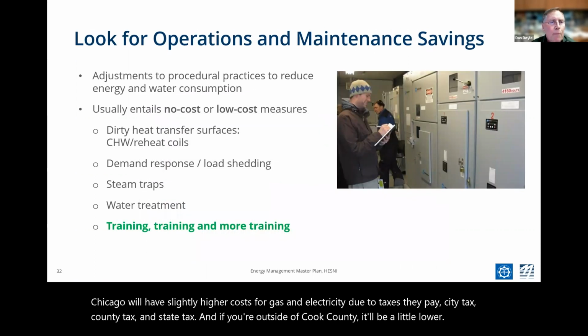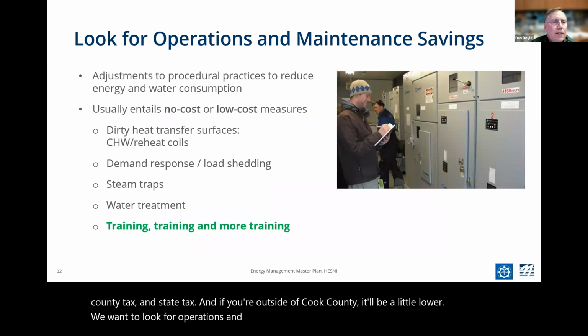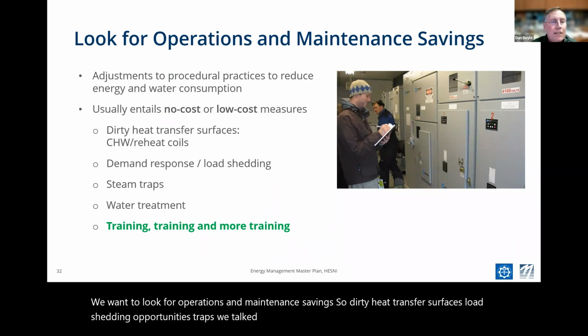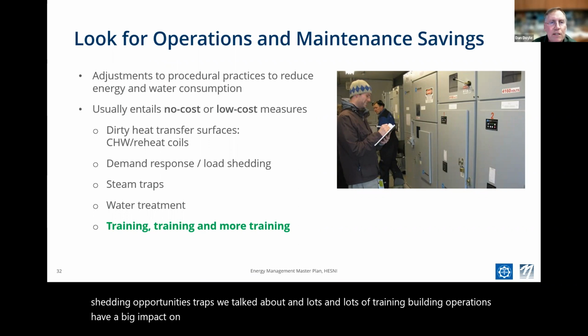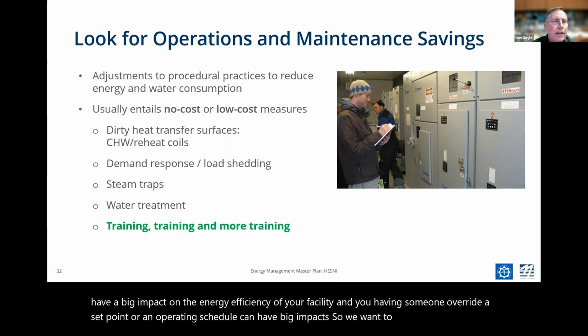We want to look for operations and maintenance savings: dirty heat transfer surfaces, load shedding opportunities, traps we talked about, and lots of training. Building operations have a big impact on the energy efficiency of your facility, and having someone override a set point or an operating schedule can have big impacts. So we want to make sure we spend money on training.